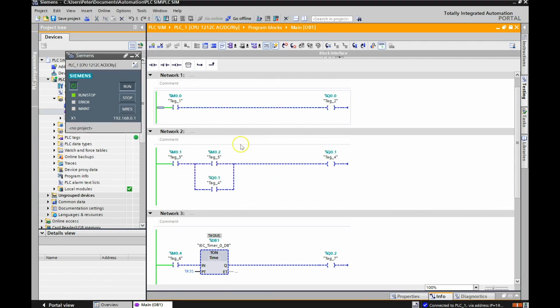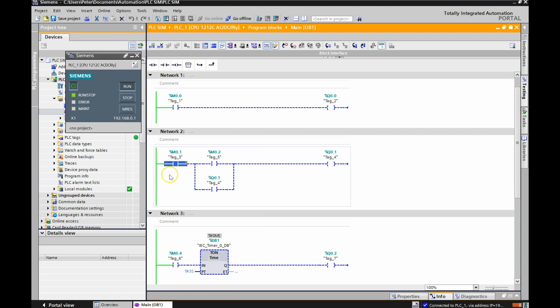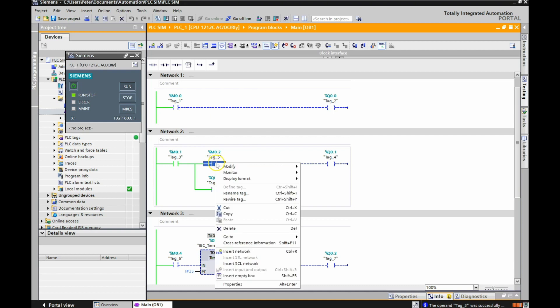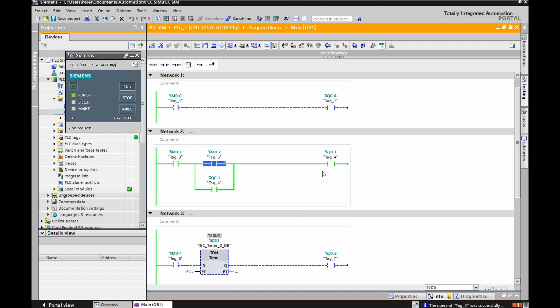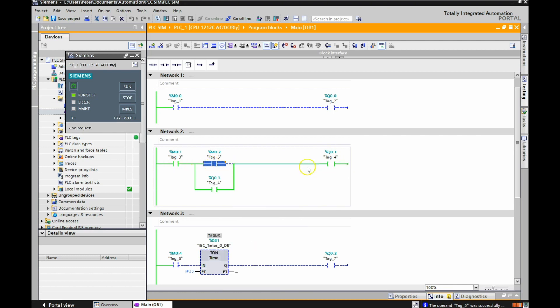Let's try the three-wire here. Here would be our Stop Push button. We're going to modify this to a 1, and you can see that the Logic Continuity is going to go to my Start Push button now. When I modify this to a 1, then my output Q0.1 should turn on. Beauty. When I modify this back to a 0, meaning that I've let go of the Push button for my Start Push button, then the Logic Continuity goes through the holding contact and goes to Q0.1. So you can see that these are linked just like they would be if we had the PLC actually running. Very cool.